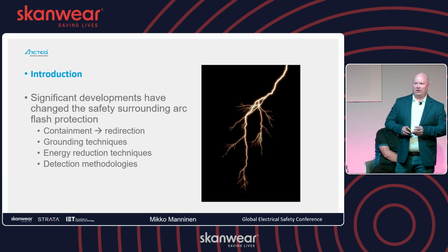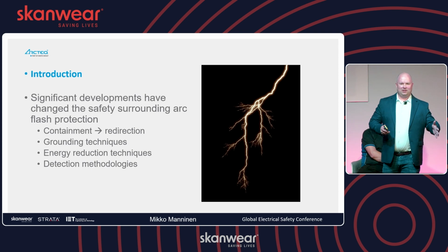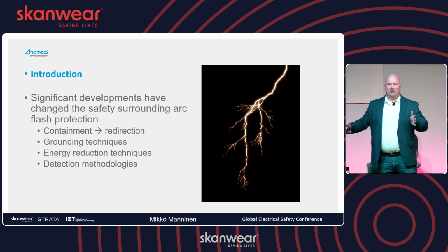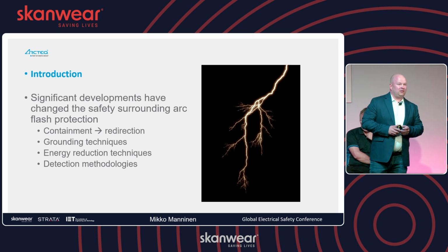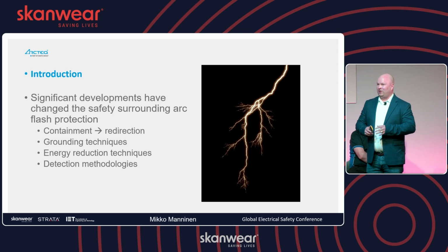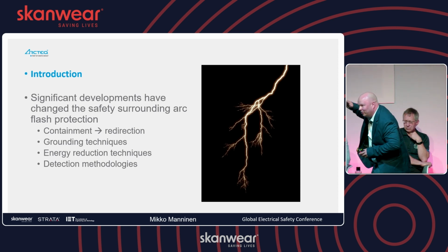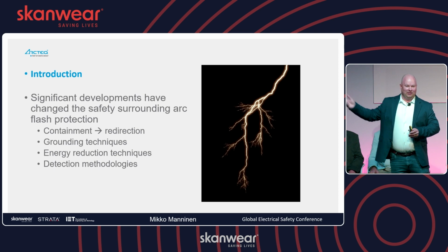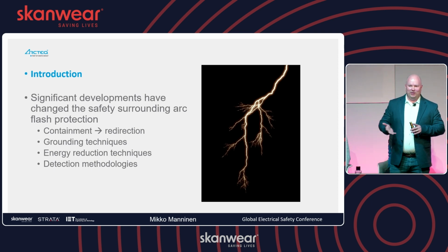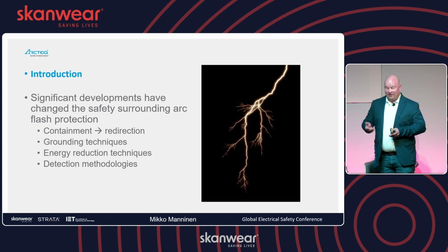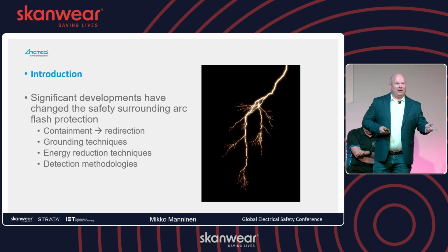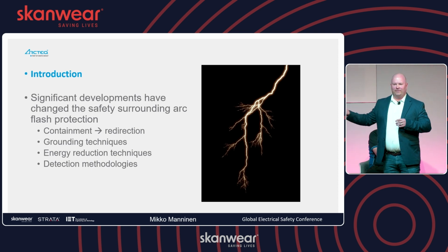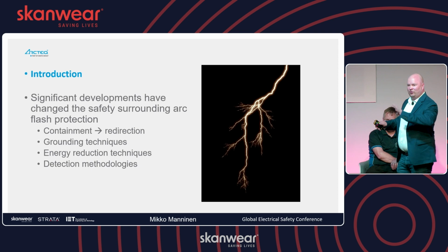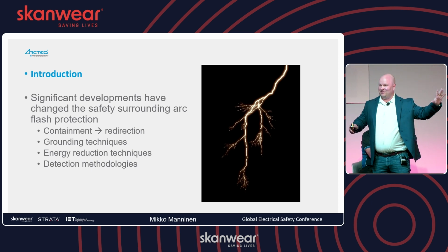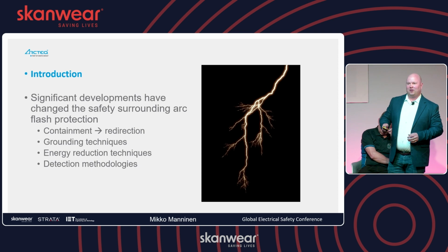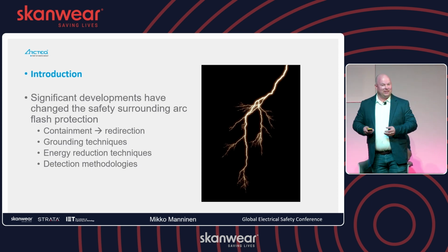Significant developments have been made over the years. There used to be concrete panels, just walls between the different cubicles, and fully open bus bars like Marcin showed yesterday. And they still exist all over the world. You can touch the bus bars. You sometimes have to crawl under it because they are so low. And live coppers, you can see it — they are painted yellow, red, probably purple, green. They are painted, but they are very dangerous. And the biggest one I have seen has been in one room, 150 megawatts in live bus bars, and you can touch those all. Sounds crazy, but that's how it was in the 1950s. A big steel plant, that was the way they built it, and it still works.